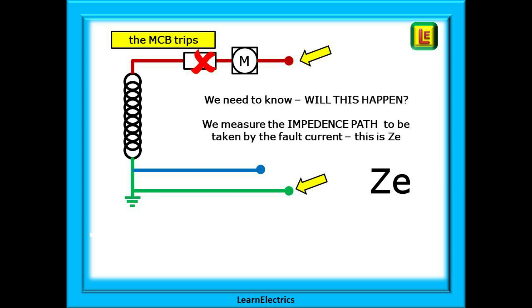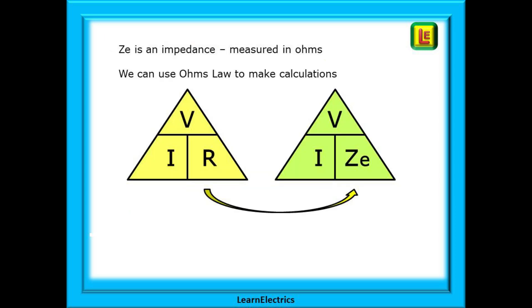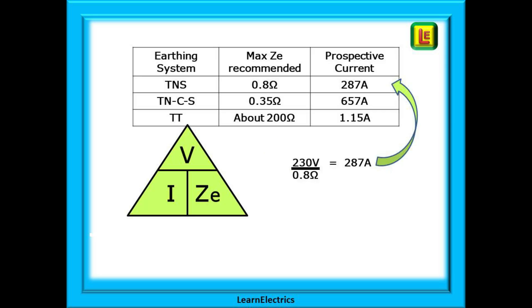And we need to know that this will in fact happen. And we do this by measuring the impedance path that the fault current will take and we call this impedance path ZE. Z for the impedance and E for external. ZE is something that you must be able to measure and it is recorded on the test certificates. We said that ZE is an impedance that can be measured in ohms and ohms law can be used. These two triangles show that voltage divided by current will give us ZE in ohms.